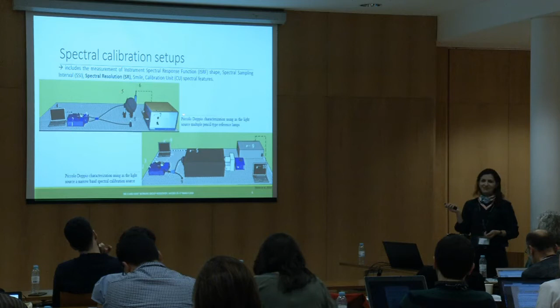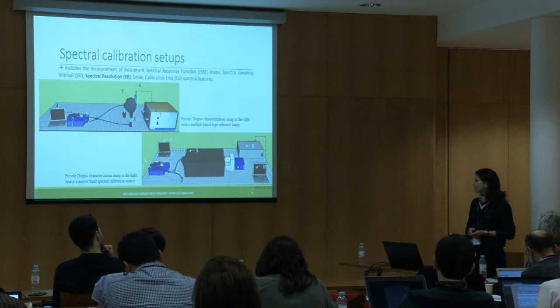But if you do so with one lamp, here it is done with an argon lamp, for example, an argon mercury lamp, and here is the spectra for the neon lamp. And if you want, for example, to calibrate the spectrometer for SIF measurements, you need to calibrate the spectrometer specifically to a wavelength that is closer to the oxygen bands, A or B. So in this case we selected the line that is closer to oxygen A. This is 763.511 nanometers. So we corrected specifically for this one. Just applying the fit, we first obtain this correction for this line, around 1 nanometer. And after that we corrected, so for that wavelength we have 0 correction.